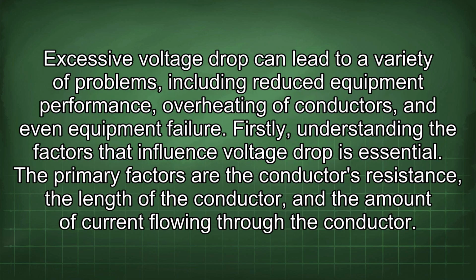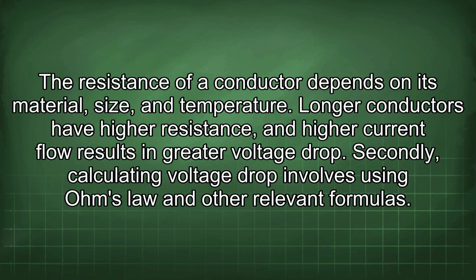Excessive voltage drop can lead to a variety of problems, including reduced equipment performance, overheating of conductors, and even equipment failure. Firstly, understanding the factors that influence voltage drop is essential. The primary factors are the conductor's resistance, the length of the conductor, and the amount of current flowing through the conductor. The resistance of a conductor depends on its material, size, and temperature. Longer conductors have higher resistance, and higher current flow results in greater voltage drop.